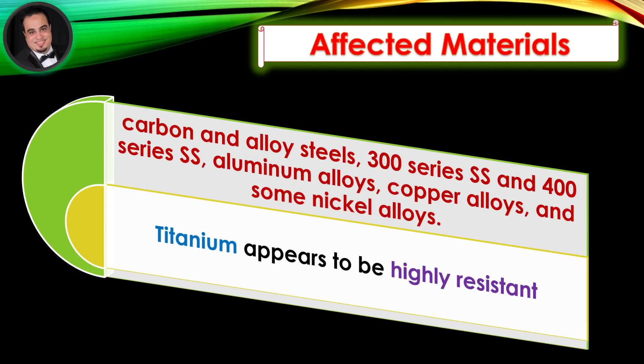Affected materials. Most common materials of construction including carbon and alloy steels, 300 and 400 series stainless steel, aluminum alloys, copper alloys, and some nickel alloys. Titanium appears to be highly resistant.